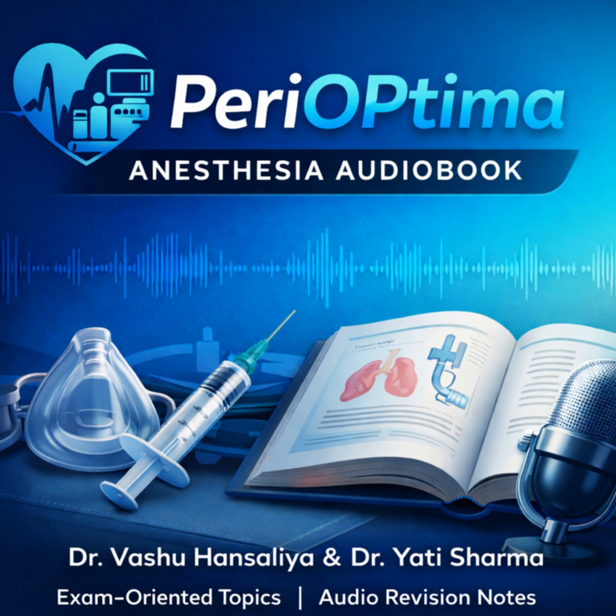We have to mention the outlier, Desflurane, the Tec 6 vaporizer. Desflurane is the problem child. Its boiling point is 22.8 degrees Celsius. That's basically room temperature in many parts of India. Exactly. If you put Desflurane in a normal variable bypass vaporizer, it would boil uncontrollably and you'd give a lethal dose. It would be completely unmanageable.